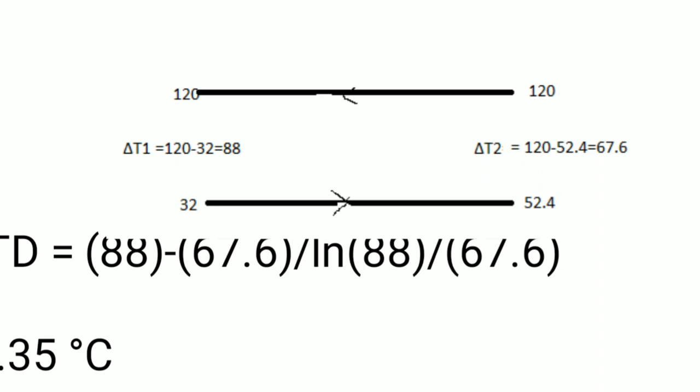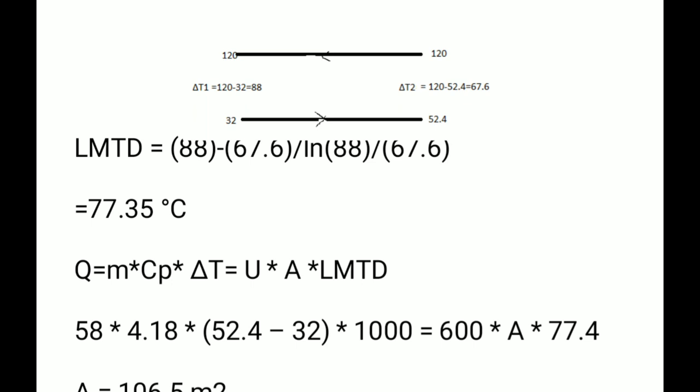In this counter-current exchanger, the hydrocarbon is condensing at a constant 120°C. Water enters at 32°C and leaves at 52.4°C. Delta T1 = 120 − 32 = 88°C and delta T2 = 120 − 52.4 = 67.6°C. Substituting into the LMTD formula gives LMTD = 77.35°C.